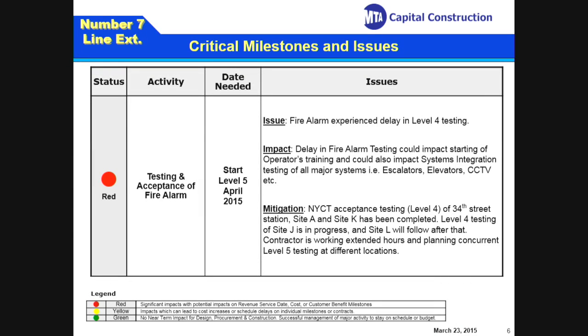The next critical issue is the testing and acceptance of the fire alarm. The issue is that the fire alarm has experienced delay in Level 4 testing. The impact is very simple: the fire alarm is on the critical path. That's our most important system right now that we're tracking.